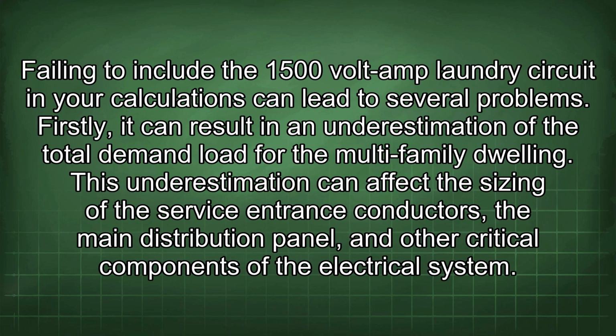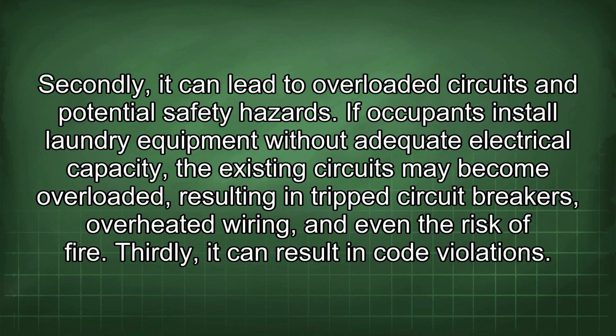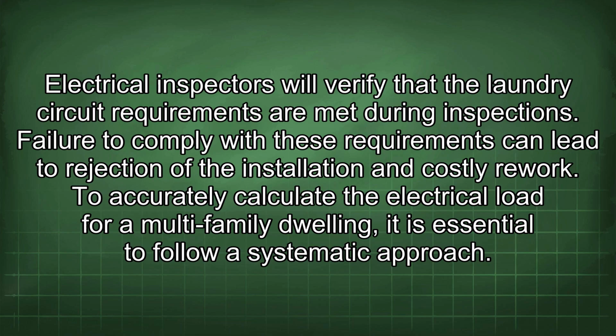Failing to include the 1500 volt amp laundry circuit in your calculations can lead to several problems. Firstly, it can result in an underestimation of the total demand load for the multi-family dwelling. This underestimation can affect the sizing of the service entrance conductors, the main distribution panel, and other critical components of the electrical system. Secondly, it can lead to overloaded circuits and potential safety hazards. If occupants install laundry equipment without adequate electrical capacity, the existing circuits may become overloaded, resulting in tripped circuit breakers, overheated wiring, and even the risk of fire. Thirdly, it can result in code violations. Electrical inspectors will verify that the laundry circuit requirements are met during inspections. Failure to comply with these requirements can lead to rejection of the installation and costly rework.